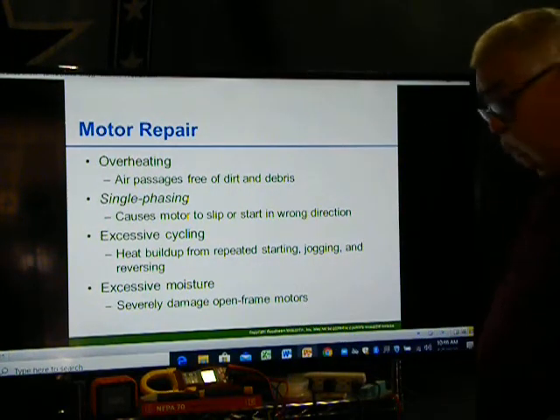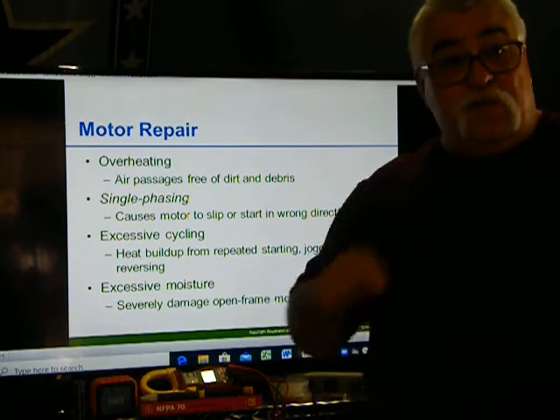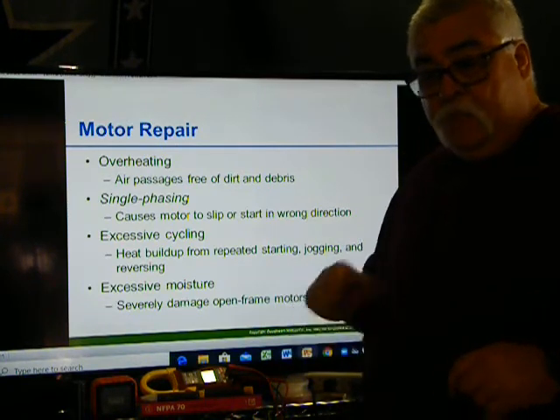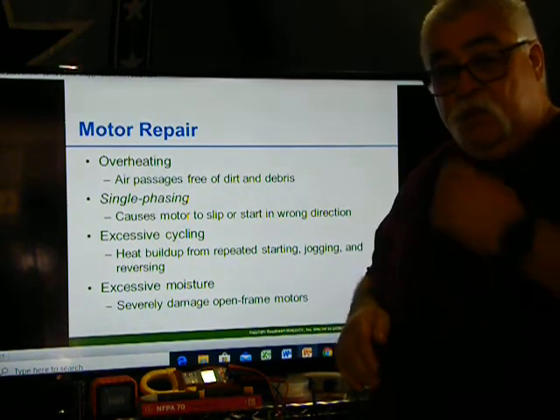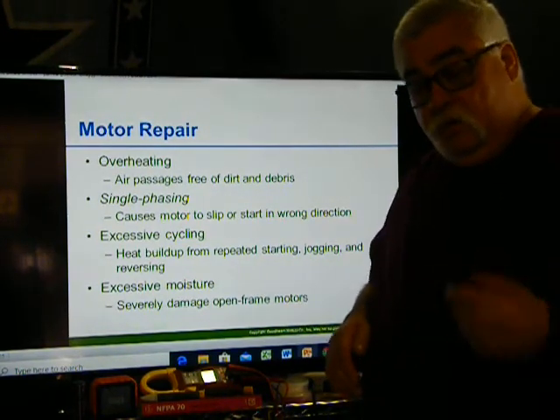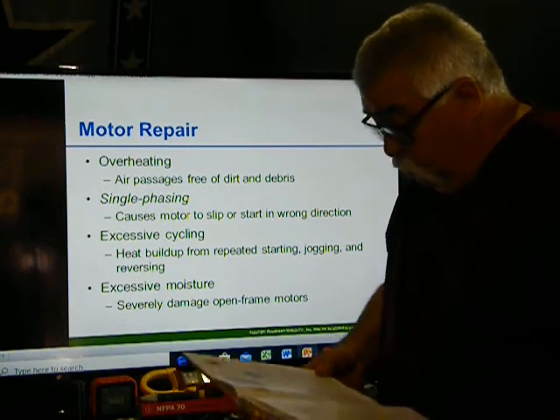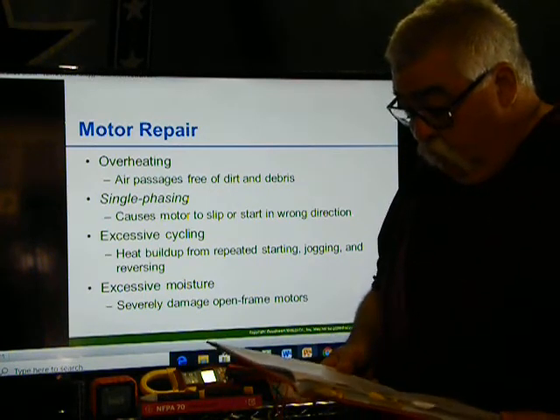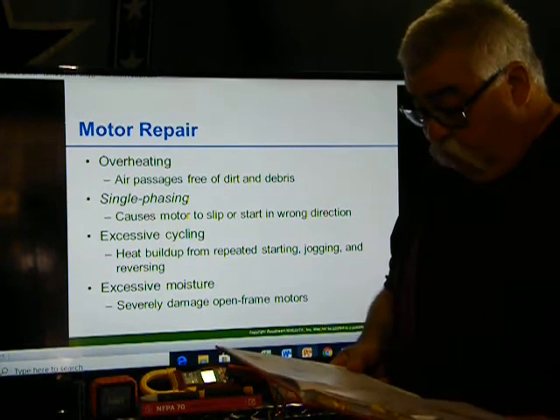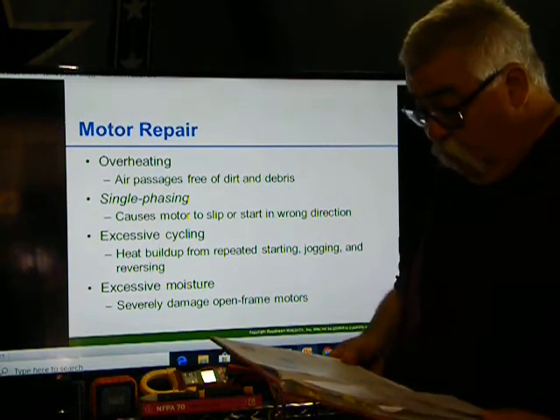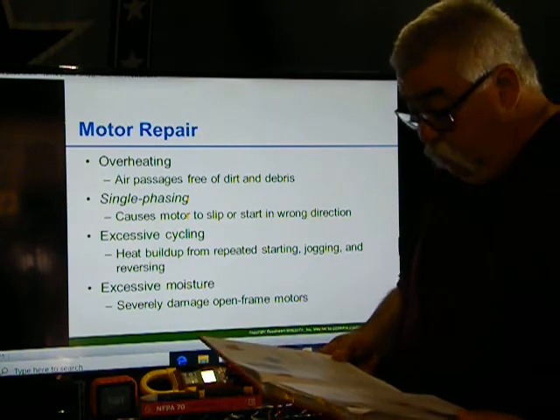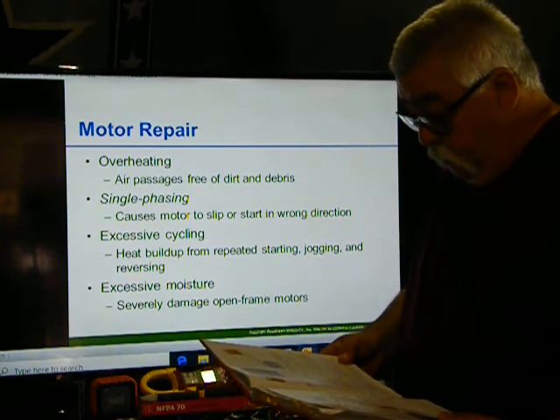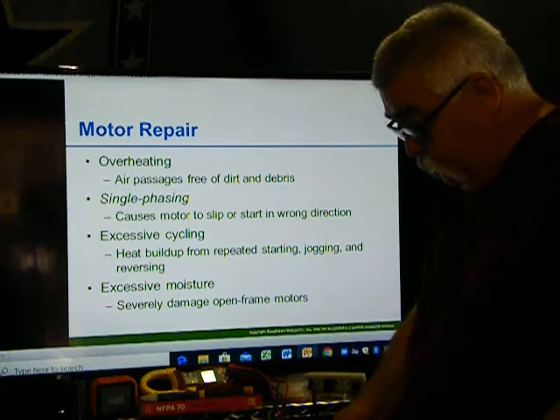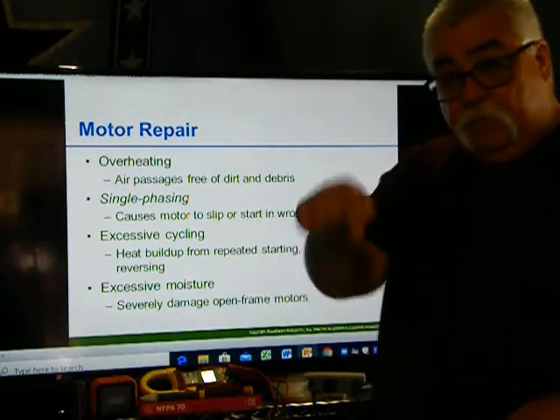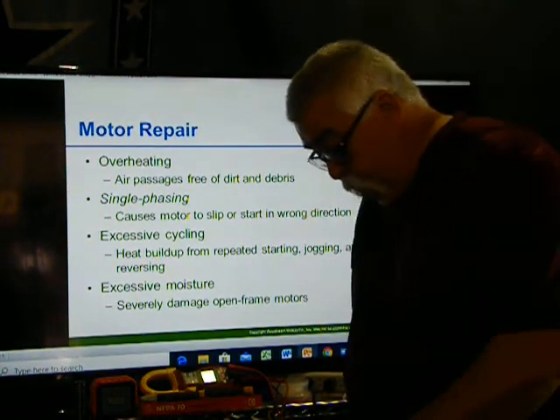Excessive cycling. Okay. So you sit there and you're jogging or playing with the buttons, and the motor doesn't have time to cool itself down. When motors are started, they draw much greater current than when they're running. Repeated starting, jogging, and reversing will not allow the motor significant time to cool. Heat buildup is certain to occur, causing the motor to burn up after a relatively short service life. So never sit there and play with the motors.